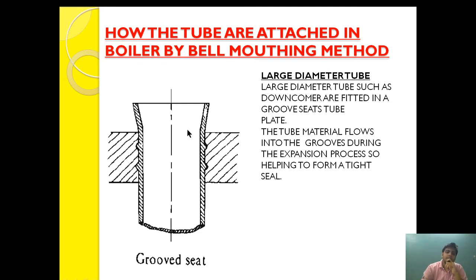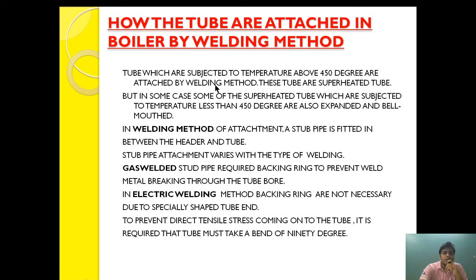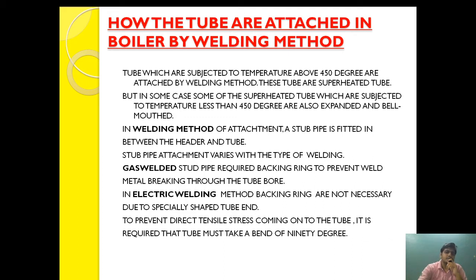Tubes which are subjected to temperatures above 450°C are attached by welding method. Superheated tubes are mainly attached by welding. If the temperature of the superheated tube is less than 450°C, then normal expanding and bell mouthing is done, but if it is above 450°C then welding is carried out.